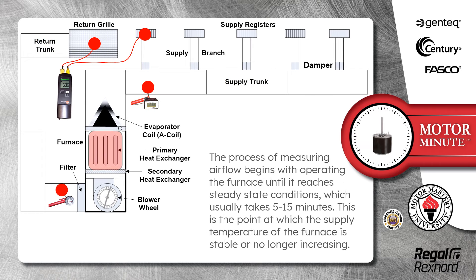The process of measuring airflow begins with operating the furnace until it reaches steady state conditions, which usually takes 5 to 15 minutes. This is the point at which the supply temperature of the furnace is stable or no longer increasing.